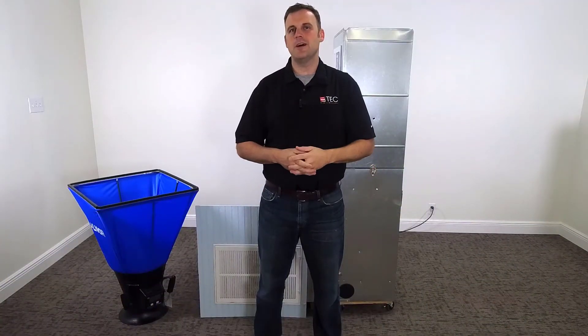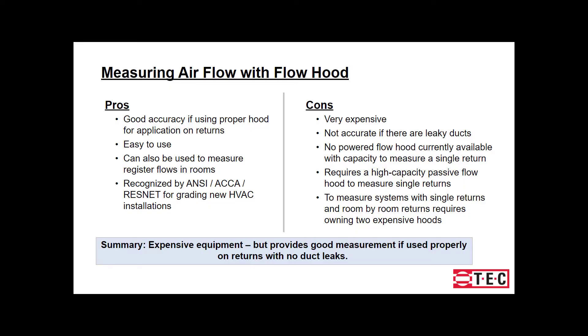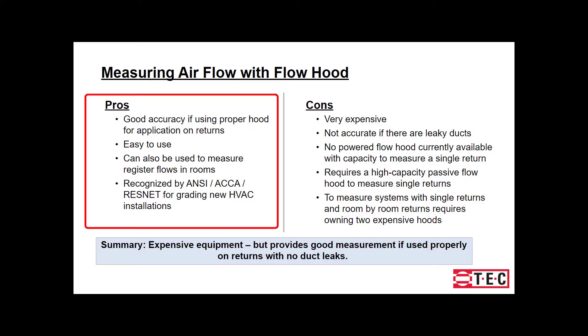Let's get into some of the pros and cons of the flow hood method. The accuracy is good if using the proper type hood for the proper application on returns. This method is easy to use. It has the capability to be used to measure register flows in rooms. And it's also recognized by ANSI ACCA RESNET for grading new HVAC installations.